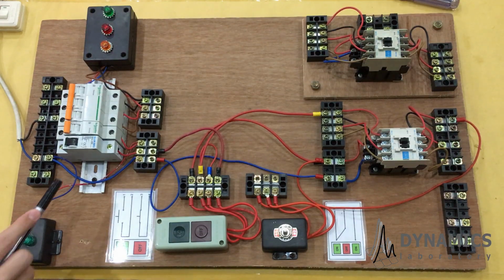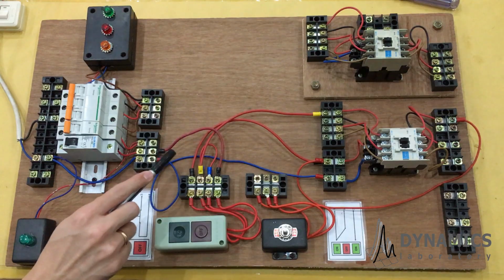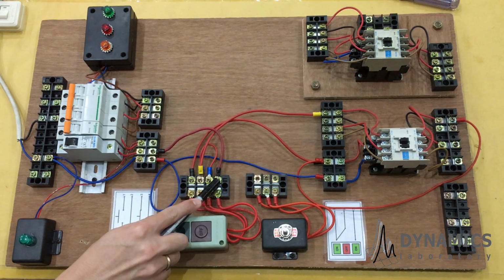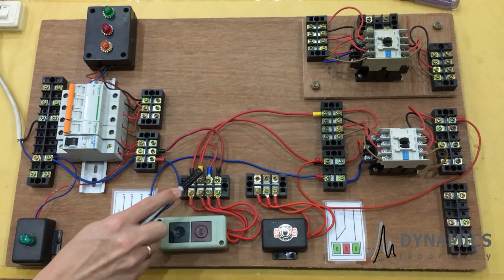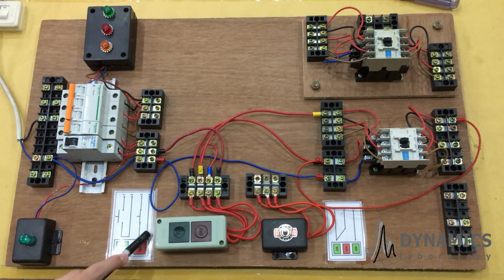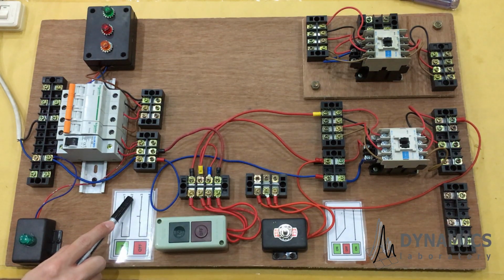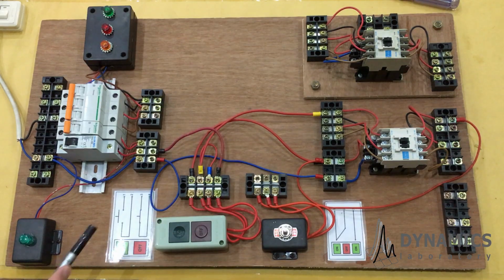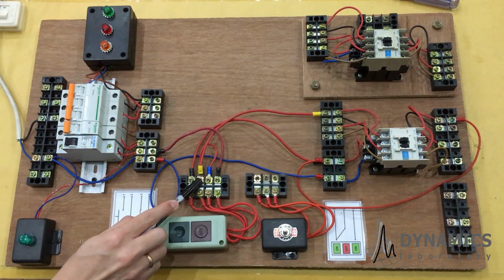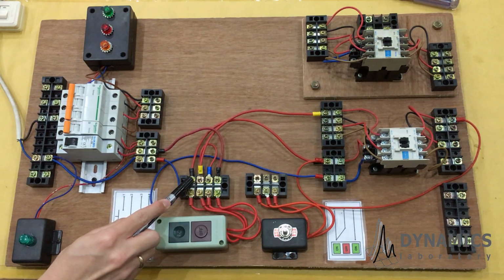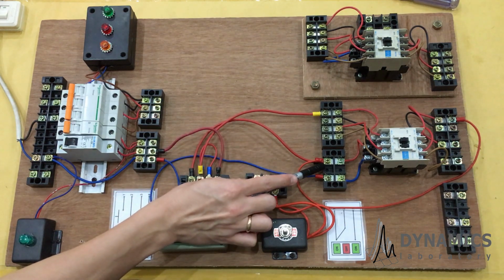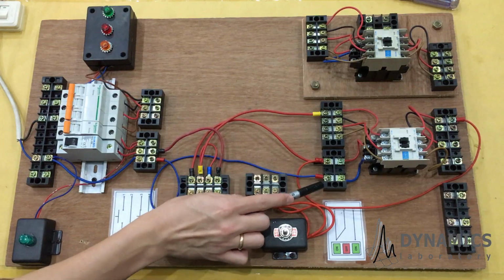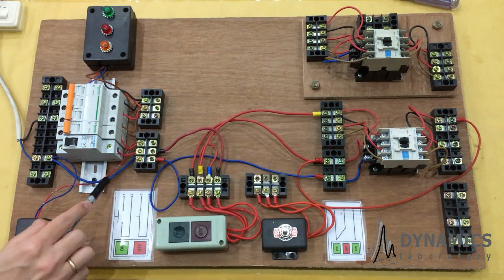Look at the circuit. From control circuit breaker to normally closed leg number 4. Then leg number 3 is connected to leg number 2, because as you see in this label, leg number 3 and leg number 4 are connected, normally closed. Leg number 1 and number 2 are connected but normally open. But leg number 2 and number 3 are not connected, that's why we have to connect them with a cable. And then leg number 1 of the push button is connected to the coil contactor in here. And then the coil contactor is connected to the neutral terminal.